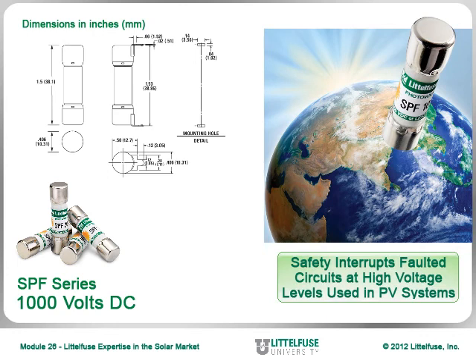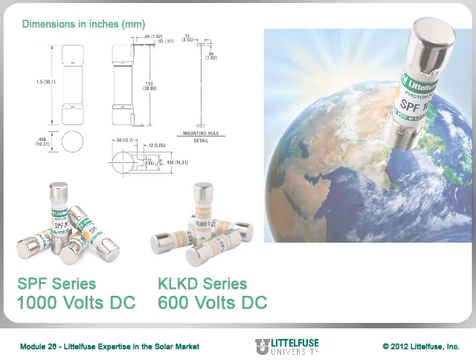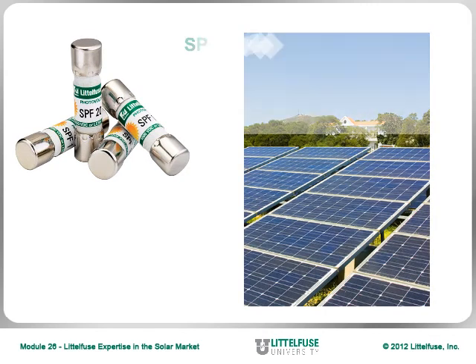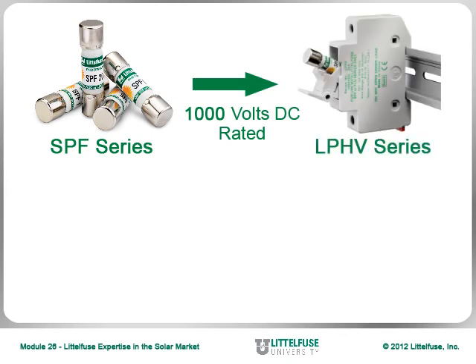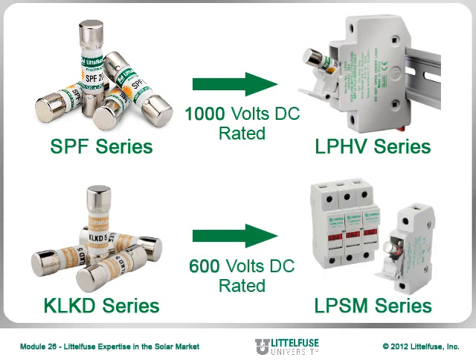The compact 10x38mm dimensions allow the 1000V DC-rated SPF series to be globally accepted while safely interrupting faulted circuits at the high-voltage levels used in PV systems, to minimize power loss associated with long conductor runs. Littelfuse also offers the 600V DC-rated KLKD series in the same physical package for lower-voltage solar applications. The Littelfuse SPF fuse safely protects PV modules and conductors in hotter-than-normal solar application environments while providing bi-directional protection in reverse overcurrent conditions. The cost-effective SPF solar fuses can be used in the new 1000V DC-rated LPHV series fuse holder, with the KLKD fuses also working in our dead-front 600V DC-rated LPSM series fuse holders.